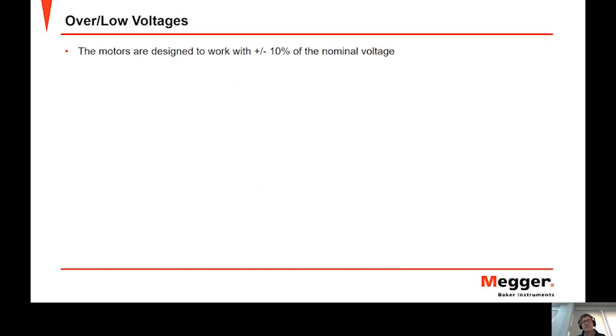Why do we care about voltage level? Well, motors are designed to work with plus minus 10% of nominal voltage, but ideally they should be less than plus minus 2%. Voltage unbalance is also crucial, and a 5% voltage unbalance can produce as much as 40% current unbalance.